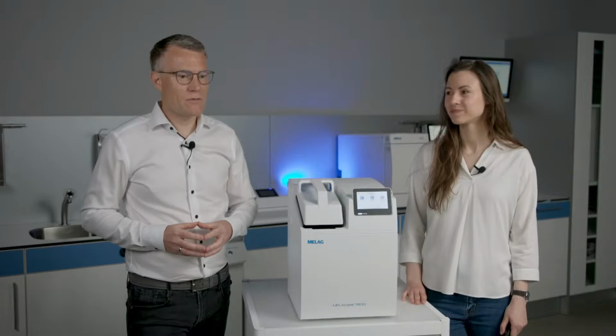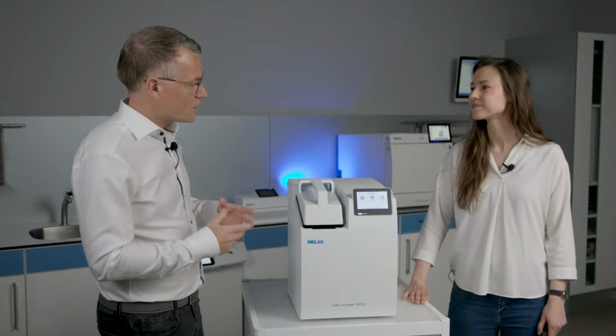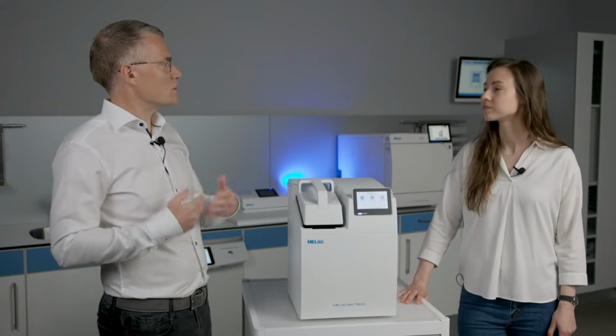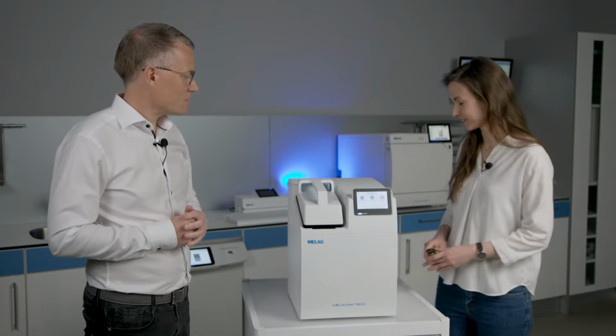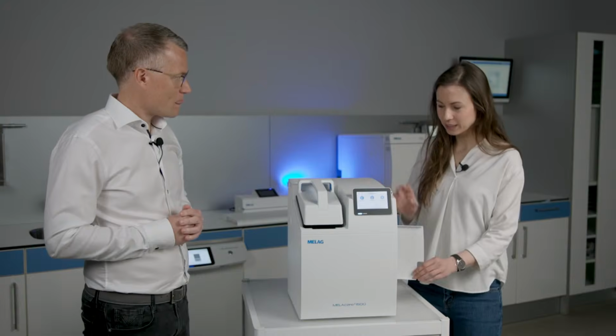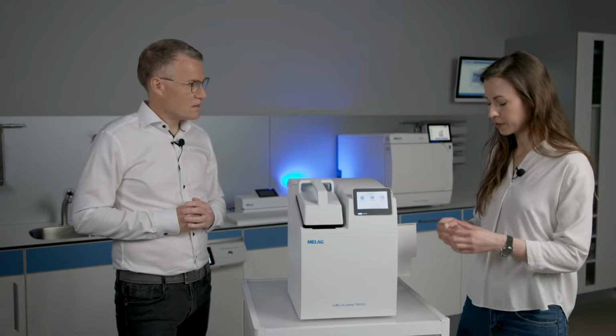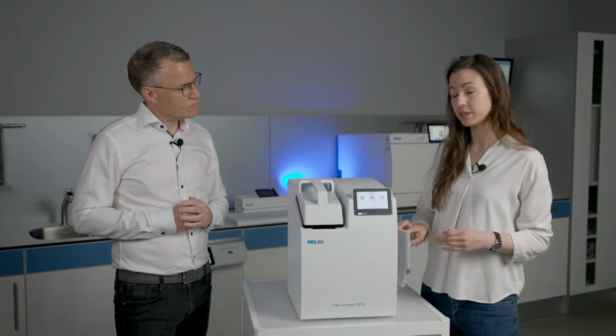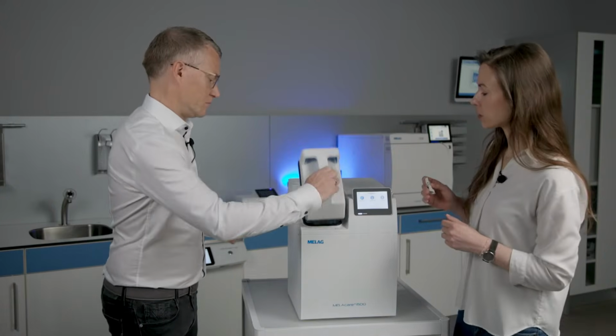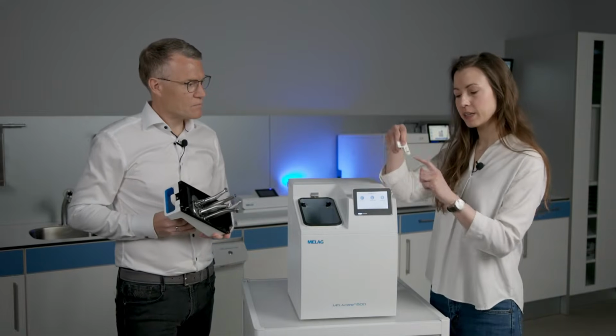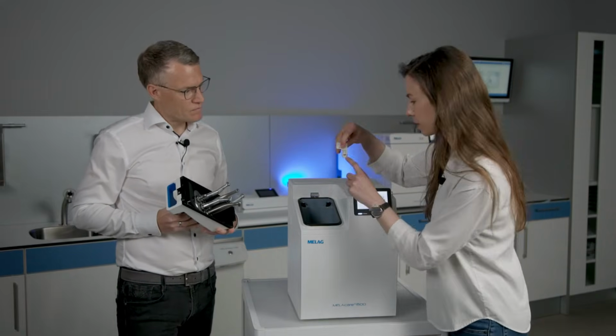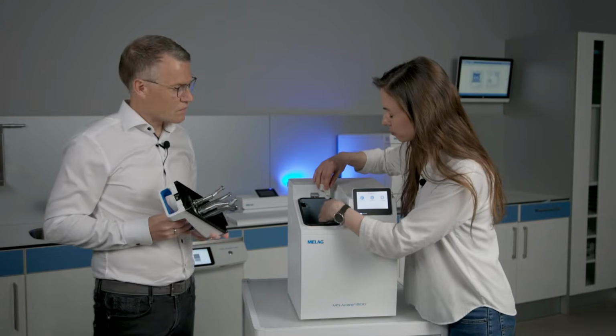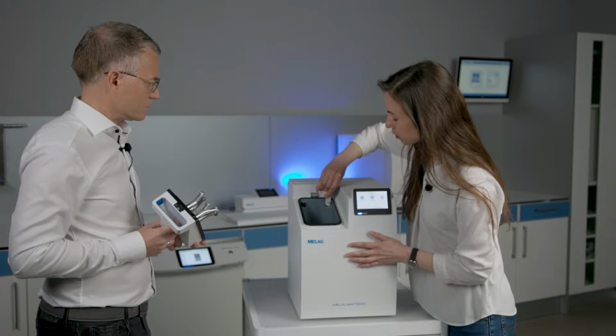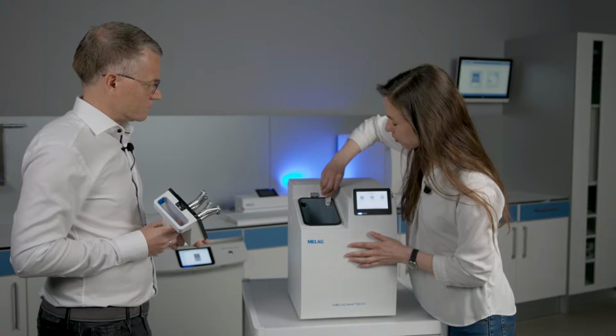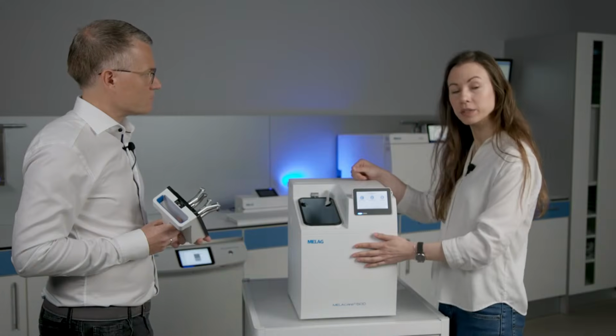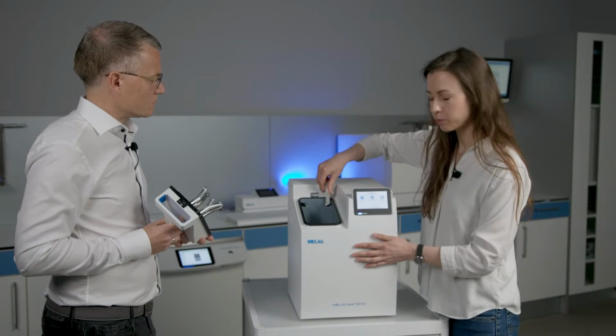There seem to be three main points that have been asked several times. The first point is if we could show in a little more detail how the chuck care actually takes place in a MELAG Care. That I will likely do. Like I mentioned before, we have our chuck care adapter located on the right-hand side of the device. Afterwards, you just take off the blue lid. There's a tiny arrow located right at the front of the adapter. You place it on the right top corner of the chamber, set it onto the black outlet, and then you just twist about 90 degrees. The adapter will actually click in place.